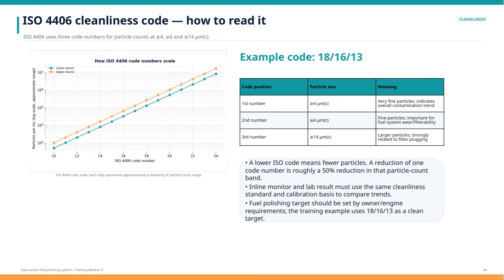For instance, an example code like 18/16/13 tells us the amount of contamination at each particle size. A key point to remember is that a lower ISO code means cleaner fuel. Each step down roughly halves the number of particles in that size range. It's essential that both inline monitors and lab results use the same cleanliness standard and calibration basis for accurate trend comparisons. Finally, the target for fuel polishing should align with the engine owner's requirements. In this training, the example clean target we've used is an 18/16/13 code. Understanding these codes will help you maintain effective cleanliness levels throughout your fuel system.